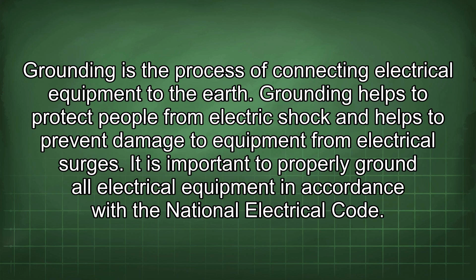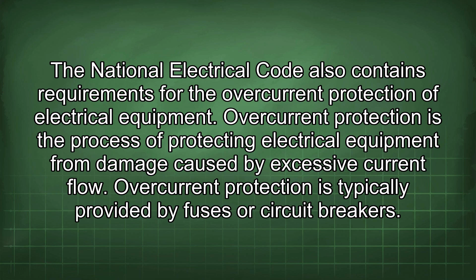The National Electrical Code also contains requirements for the overcurrent protection of electrical equipment. Overcurrent protection is the process of protecting electrical equipment from damage caused by excessive current flow, and is typically provided by fuses or circuit breakers. It is important to properly size and install overcurrent protection devices in accordance with the code.